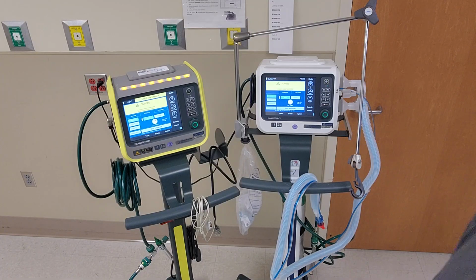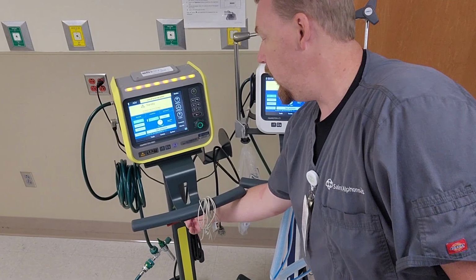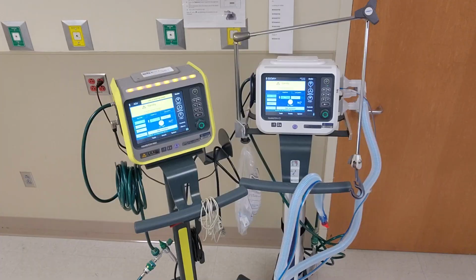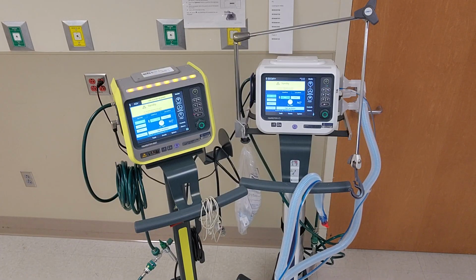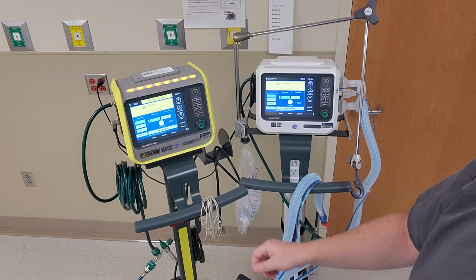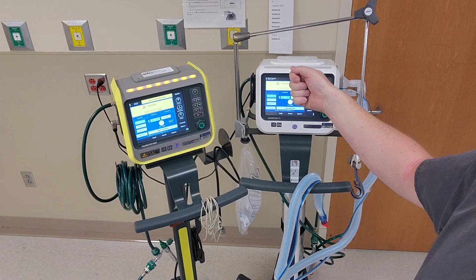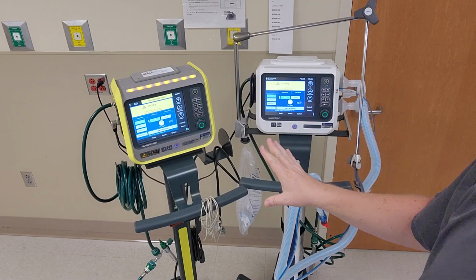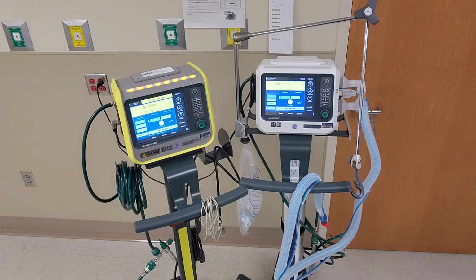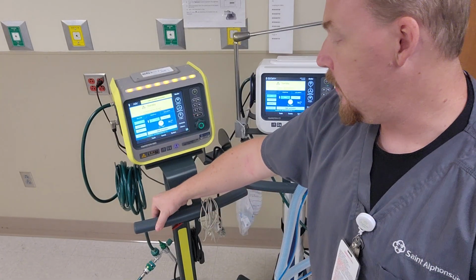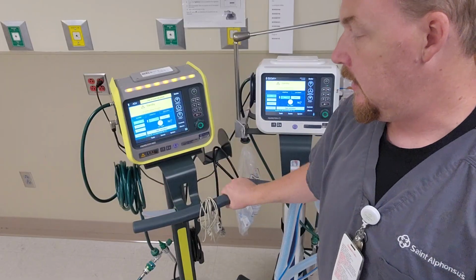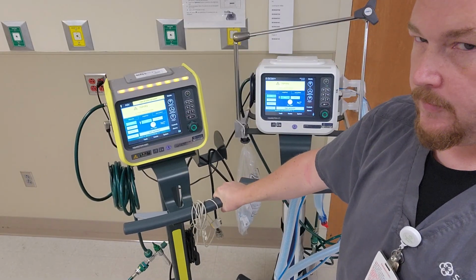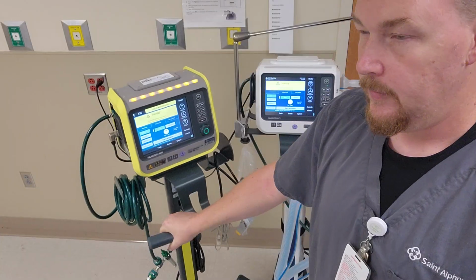Now on the front of here, right here, there's this little hook, or little eyelet I should say. We're going to have a tether attached to the MRI, in the MRI. So you'll see the tether attached here to the machine. When you first get in there, clip that little tether up to the wall, and I can guarantee you that that machine will not get close enough to the MRI that it will actually cause any damage. Also, when you do get into that suite, make sure you unlock the brakes. So squeeze the handle and get that unlocked, so it will not move without you actually pulling the handle. See, there you go.